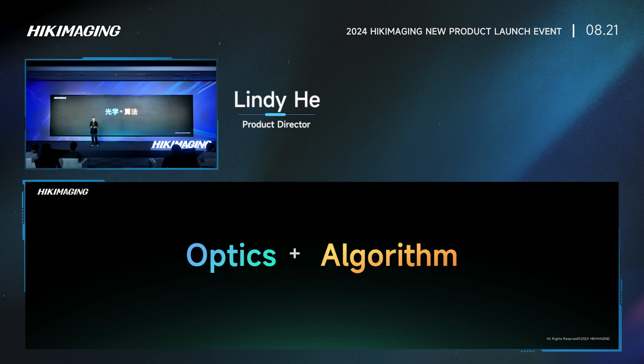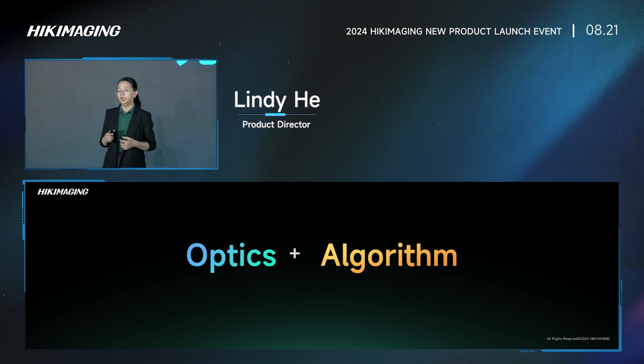The 3D fluorescence issue is similar to the 2D. Fortunately, the experience we have accumulated in 2D fluorescence can also be applied to 3D. As we mentioned earlier, we optimized both the optical and algorithm parts to make 2D fluorescence better, and we applied the same strategy to 3D fluorescence. For example, we designed a 3D lens with reduced transmittance loss, better lens filtering, and algorithm gain control strategies, as well as the support of the ISP version 2 algorithm, which has resulted in positive feedback from a local clinical trial for our 3D fluorescent product.